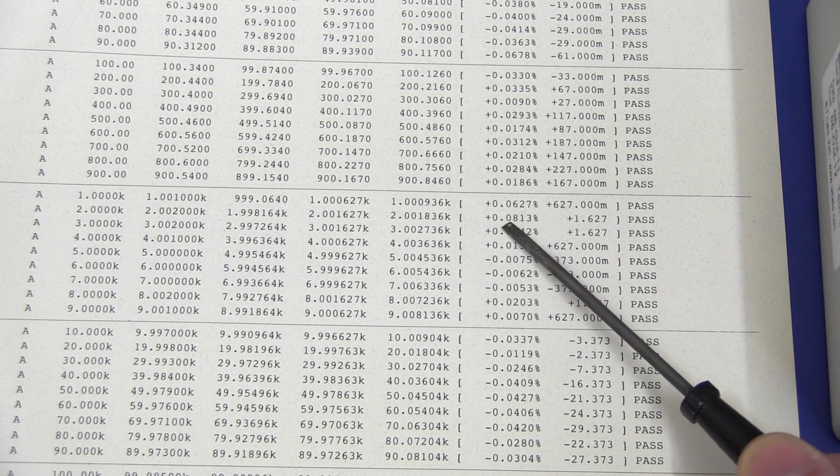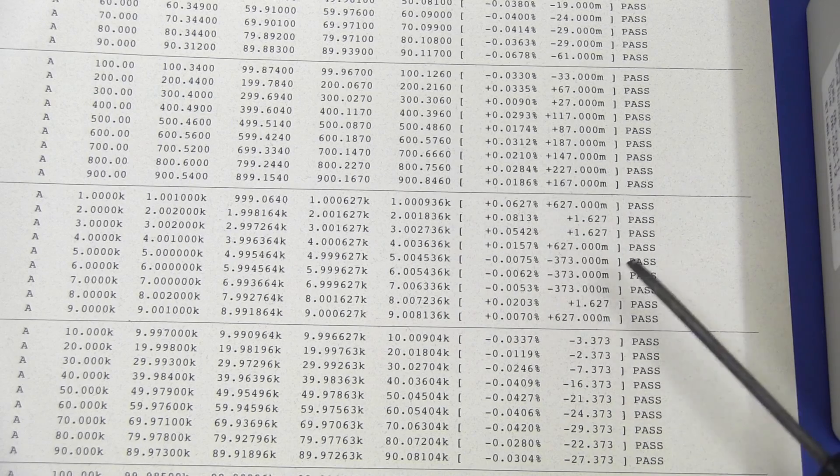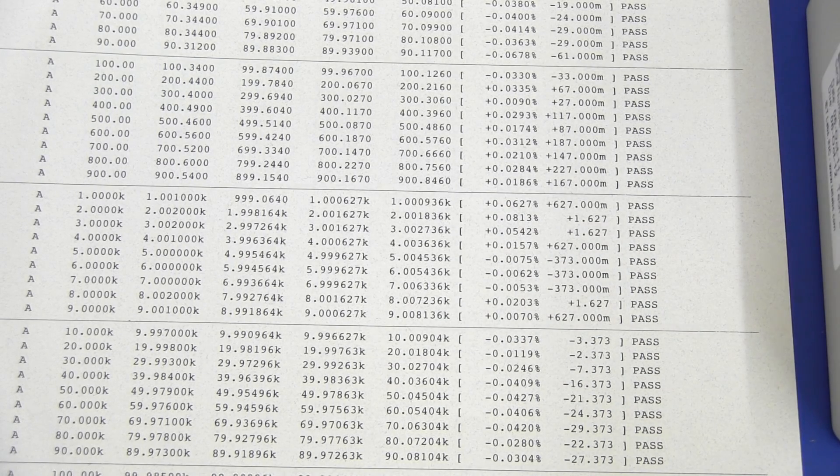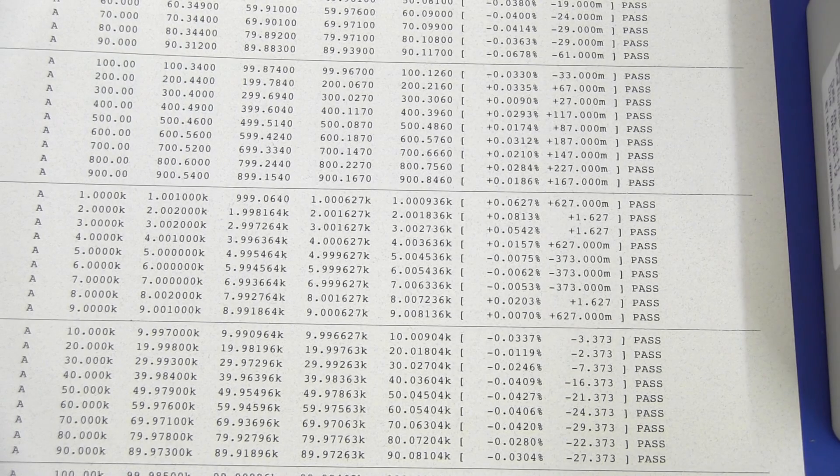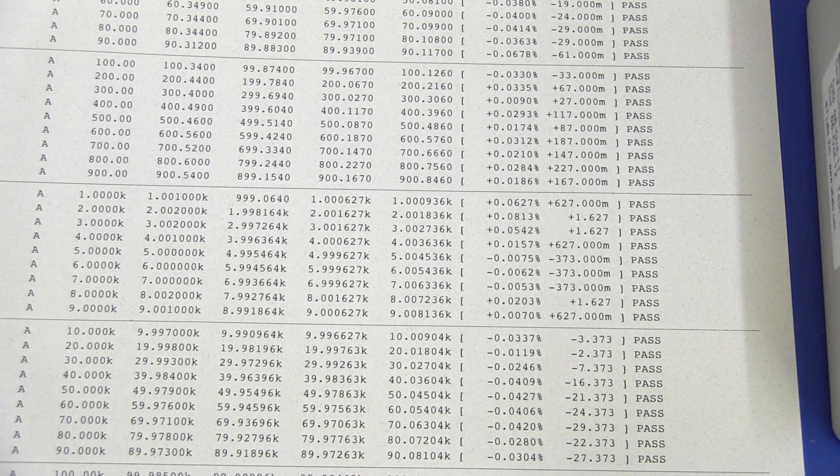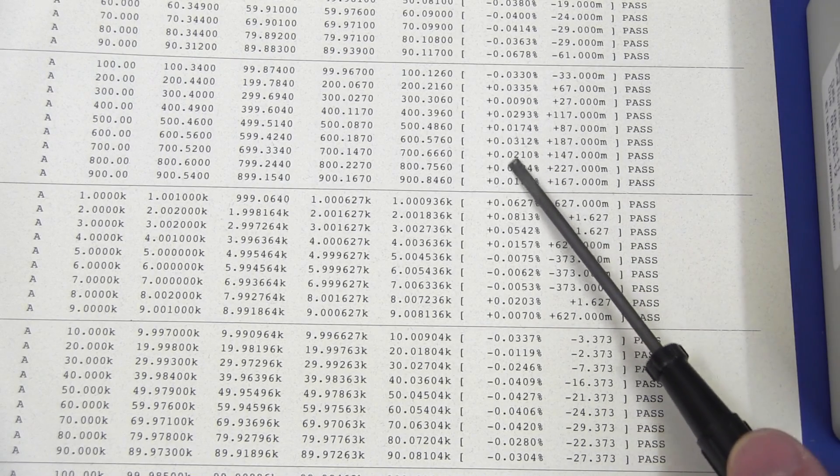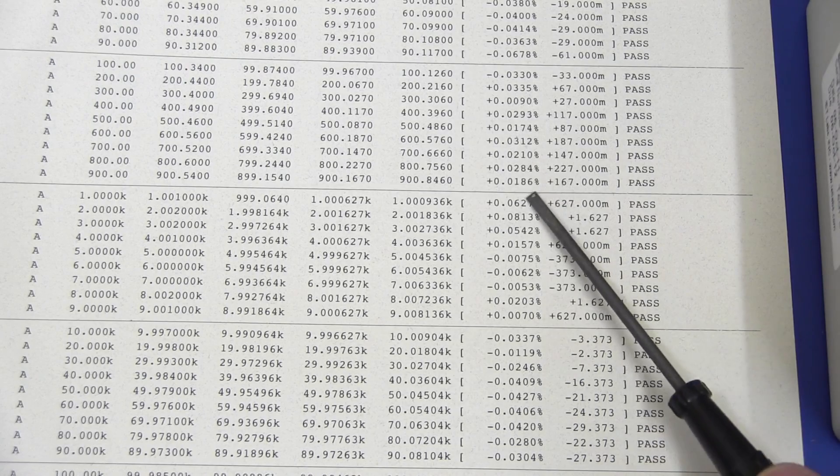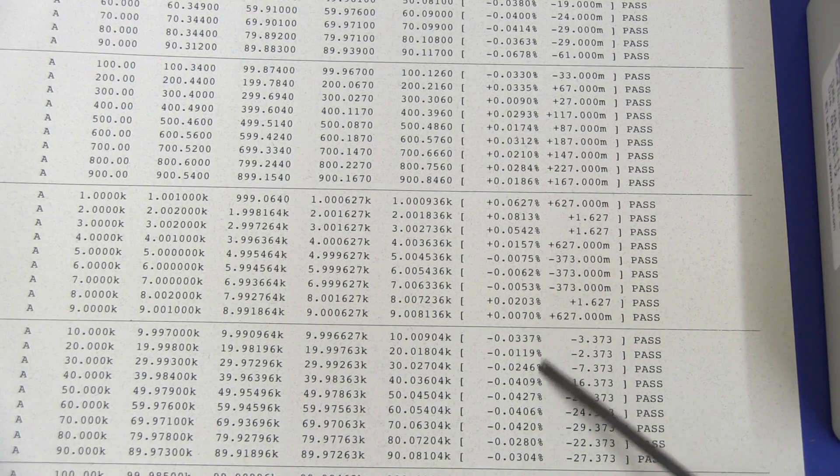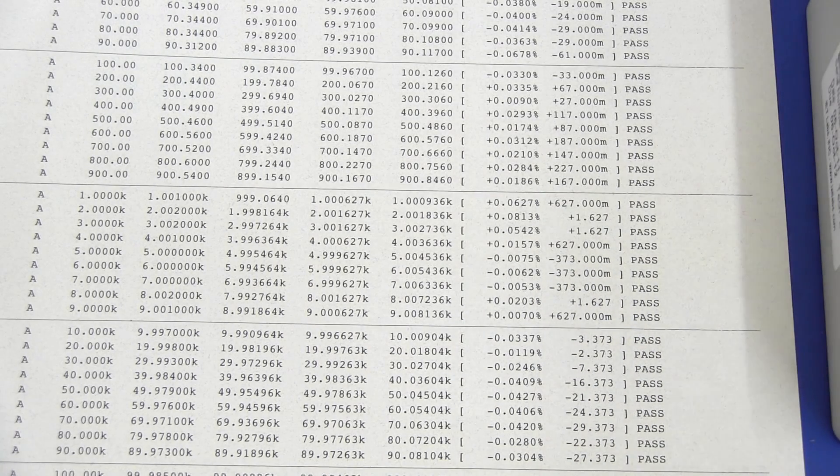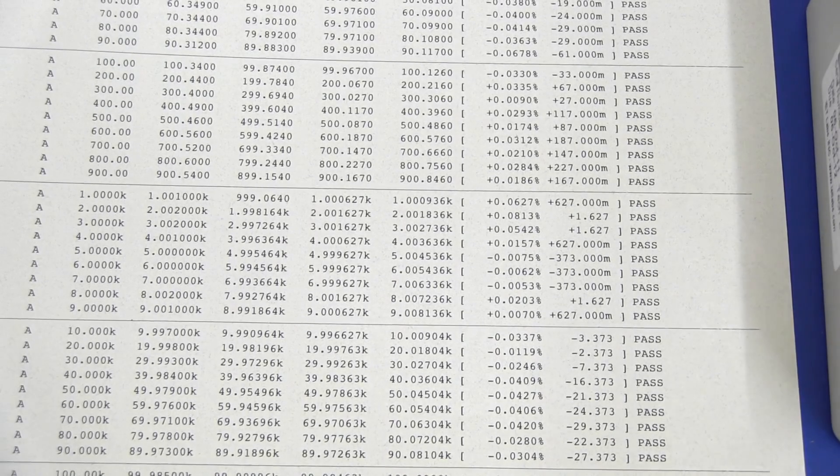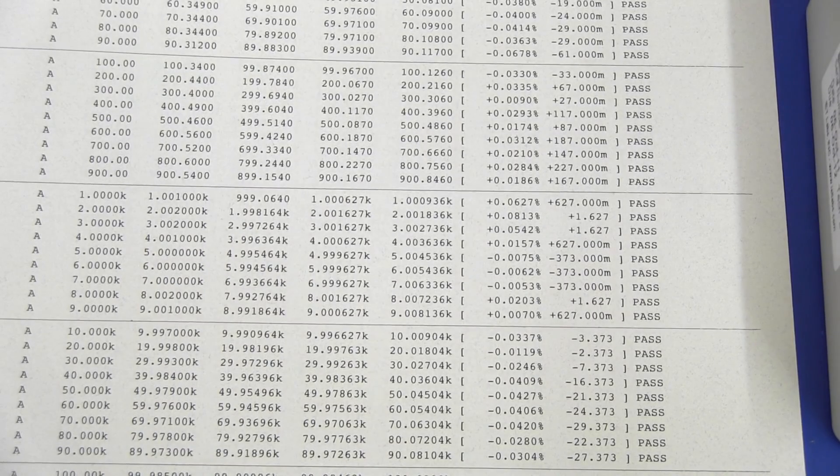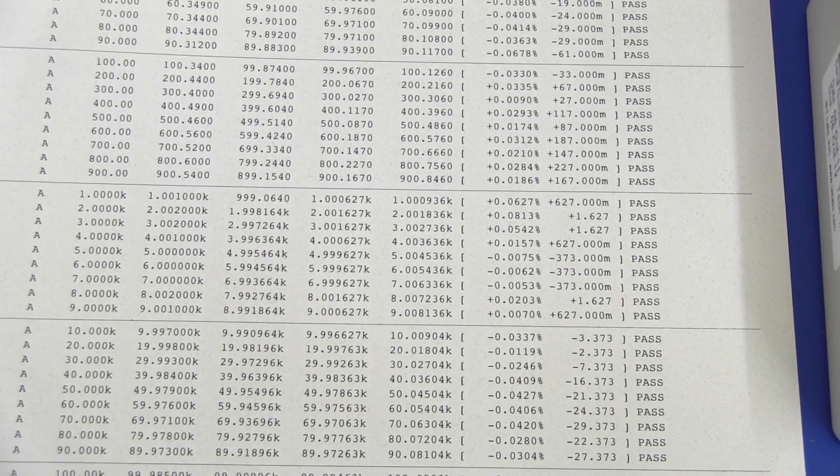But of course, they were all going to pass, they wouldn't sell it to you if it didn't meet its absolute spec of 0.1%. But as you can see, a good majority of these figures are around the 0.01, 0.02 range. So it's pretty good. But that's what you'd expect. You wouldn't expect them to actually, or a good majority of them, to be close to the 0.1% tolerance.